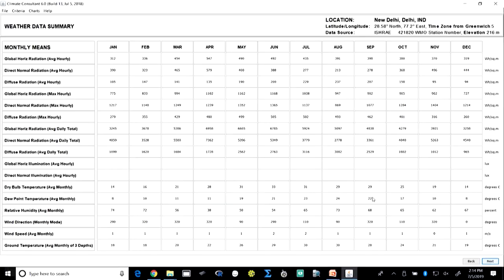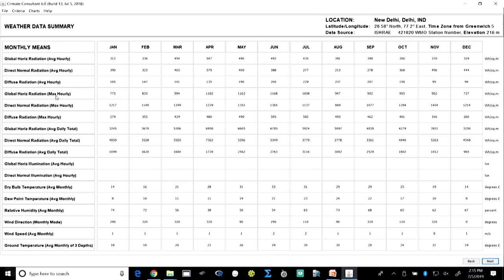Once we open the weather data file, we see the entire data spread. We have global horizontal radiation, direct normal radiation for each of the months, diffused radiation, and global horizontal radiation at maximum, average monthly, average daily, and average hourly levels. Besides radiation, we also have illumination, dry bulb temperature, dew point temperature, relative humidity, wind direction, wind speeds, and ground temperature at average monthly values for three depths underground. This is the summary table shown as the first screen after loading the weather data file.